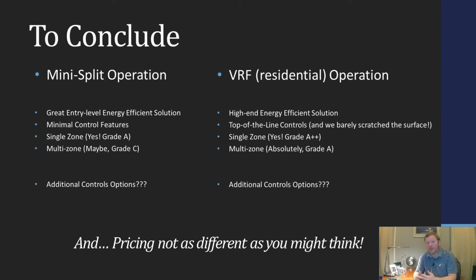overshooting. The one thing I'll tell you though is be careful, because a lot of the thermostats that you add to mini splits will manually turn off the indoor unit as soon as it reaches the set point at the thermostat. It full on turns the unit off. And this is okay in most cases, except a lot of your multi-zone mini splits change which indoor unit is the master when a head is turned off. So you can very easily lose or get confused which unit's controlling the mode of the heat pump system if you have any of them in auto. And usually once you add thermostats, you put them in auto. So you do have to be careful, but out of the box, you're going to have the handhelds and you have very, very minimal control options.